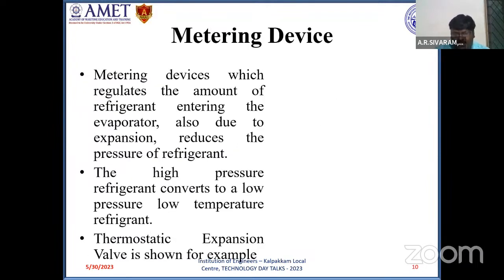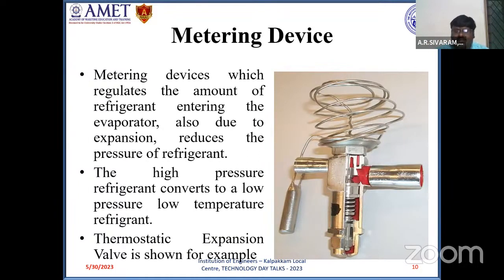So followed by the receiver, there is a metering device. The metering device controls the flow of refrigerant entering the evaporator. Normally, depending upon the cooling load in the indoor unit, a thermostatic expansion valve is given here, for example. Depending upon the variations in cooling load, that is, the amount of heat that needs to be removed from the indoor unit, this metering device alters the pressure or flow of refrigerant. Apart from this, due to sudden expansion in the metering device, the high pressure liquid refrigerant which enters it undergoes expansion, and due to sudden expansion, the refrigerant leaves as a low pressure, low temperature liquid vapor mixture.